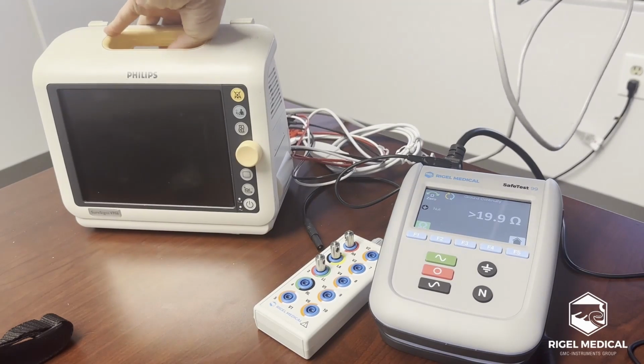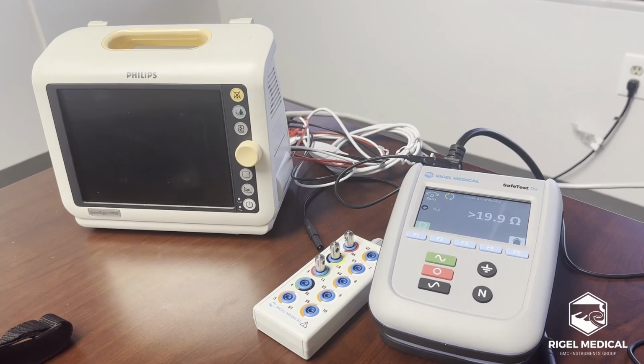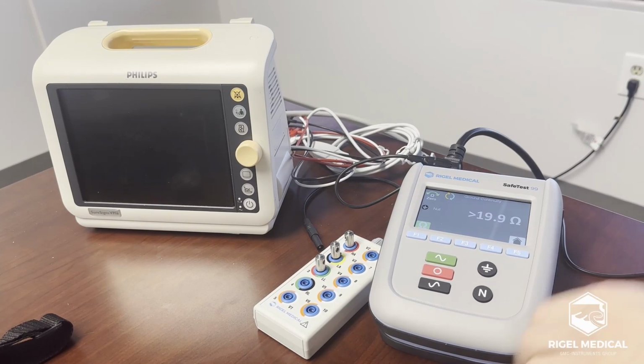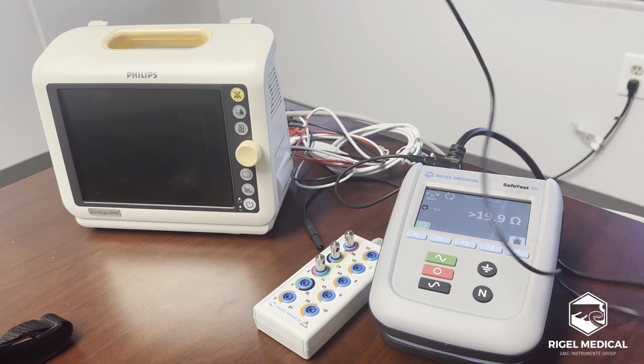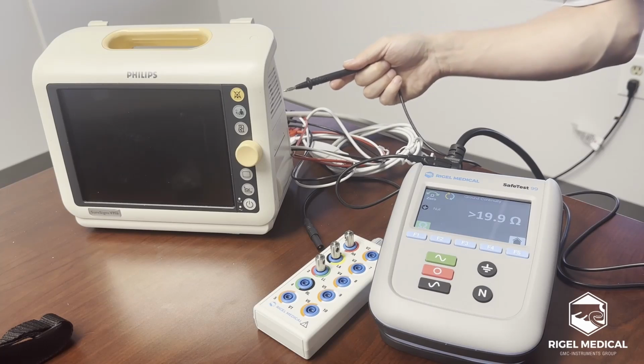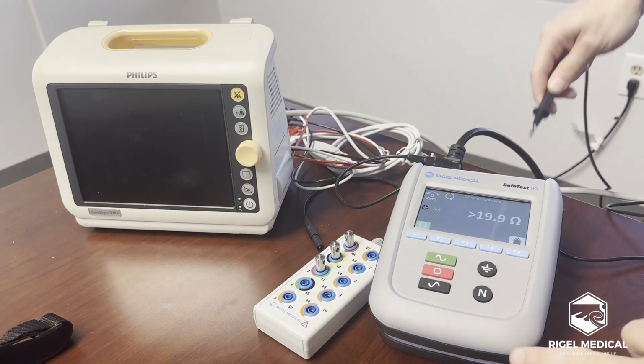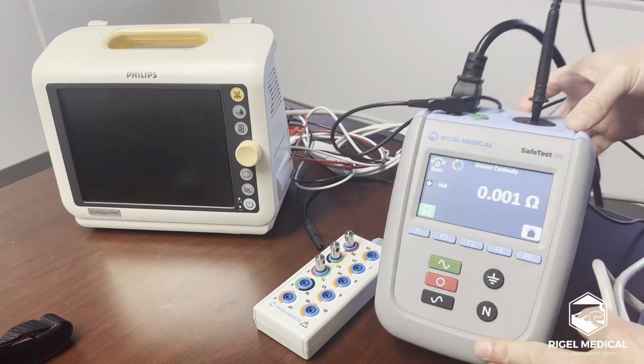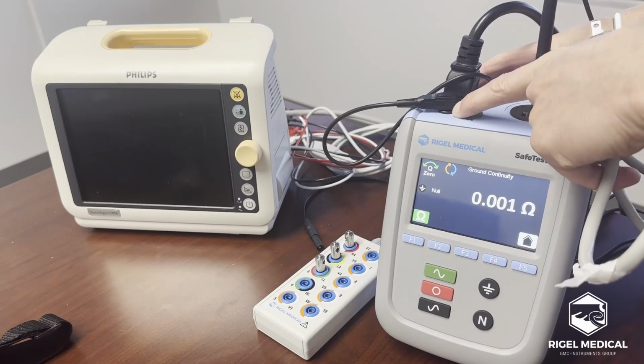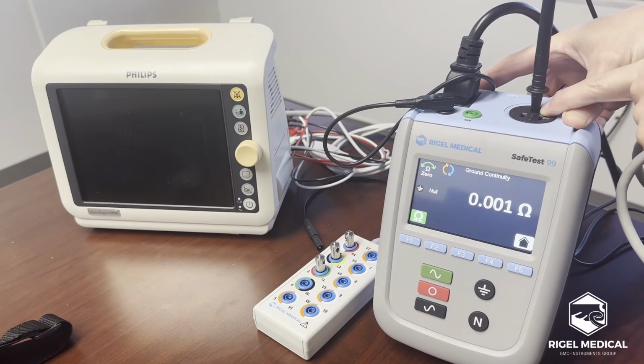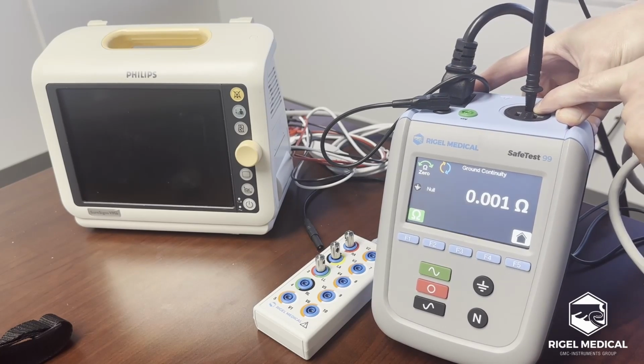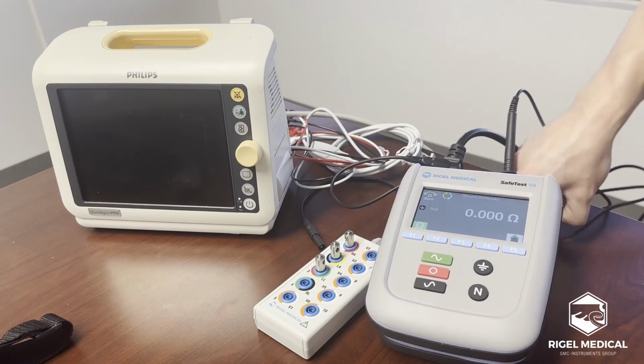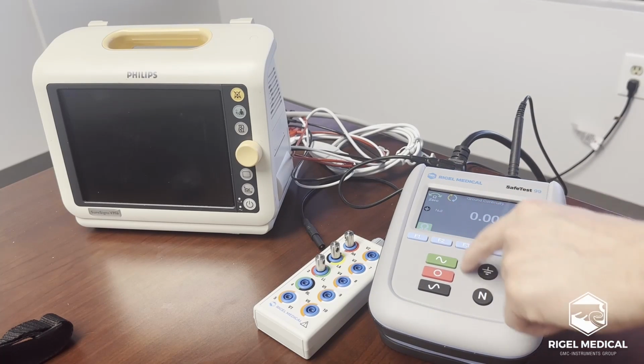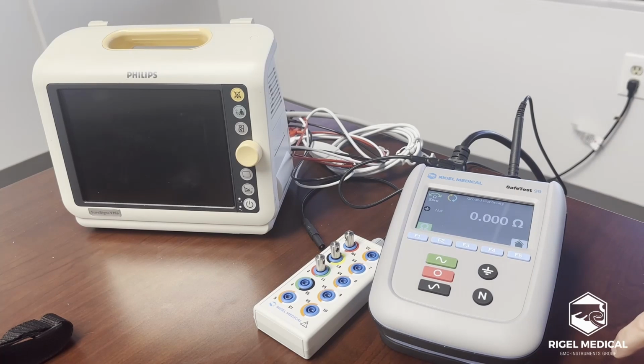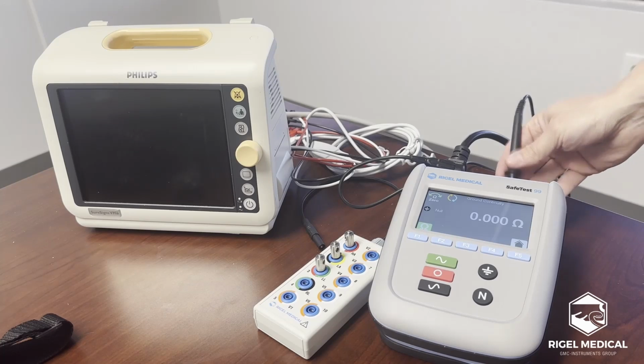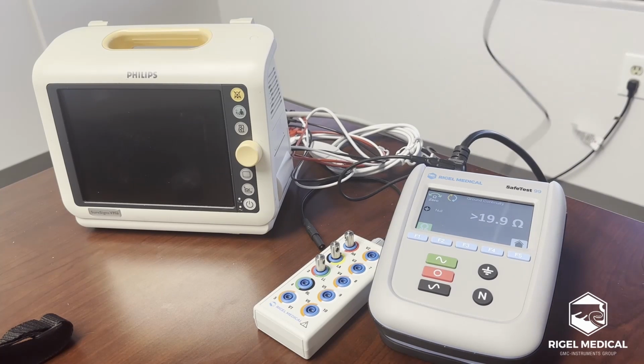So I've got my medical device here. Make sure you can see that all okay. Looks good. I did disconnect the alligator clip because this device doesn't have a point where I can connect the alligator clip, so I'm just using the 4mm probe. So I'm going to zero that out again. So I connect the probe between the black 4mm socket on the SafeTest 99 to the ground receptacle on the device under test. Still close to zero. I think we're okay, but I'm just going to zero it out anyway. Now I can test ground bond.